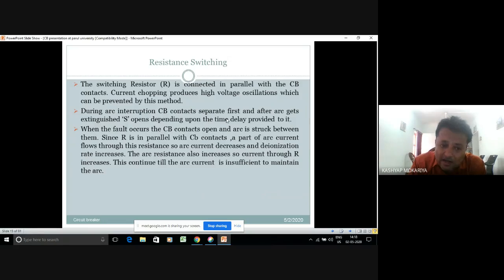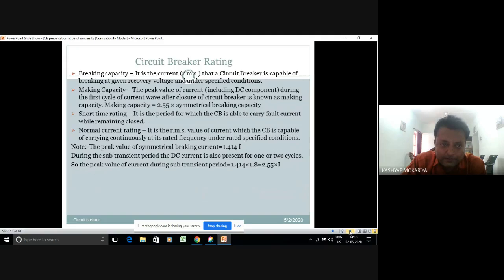A part of the current now flows through the resistance. So the arc current will get decreased because you have a parallel path through R in parallel to the breaker contacts. So the arc resistance also increases, so current through R increases. This continues till the arc current is insufficient to maintain the arc. Thus, this is how we can deal with the current chopping phenomenon.